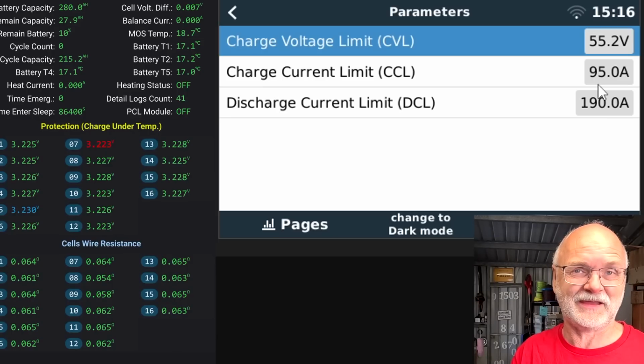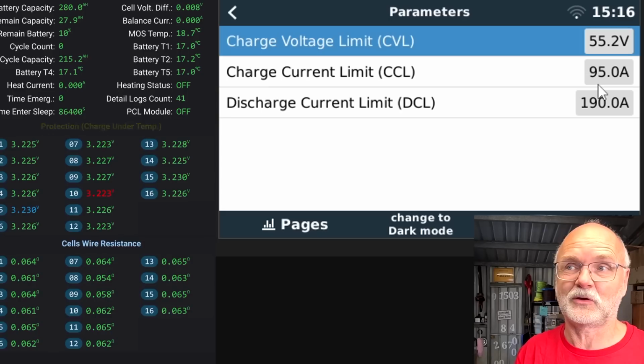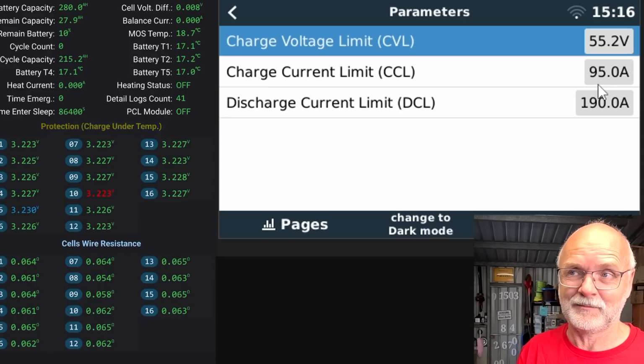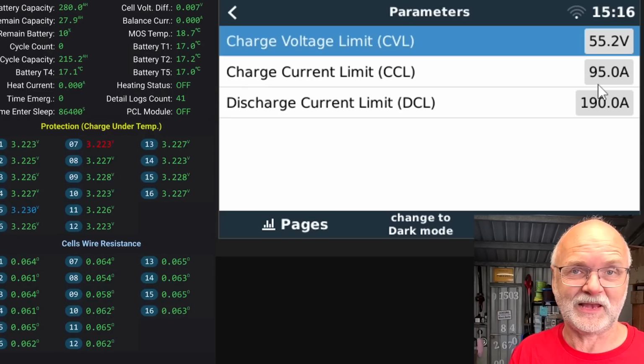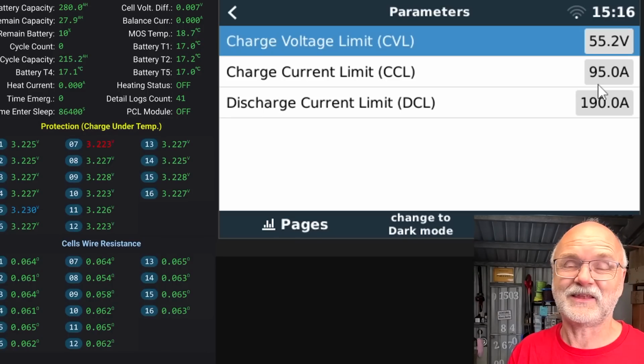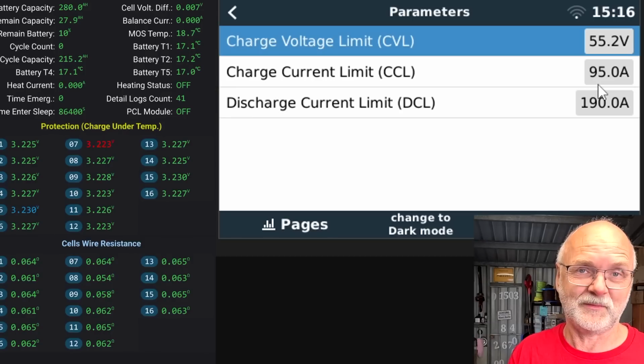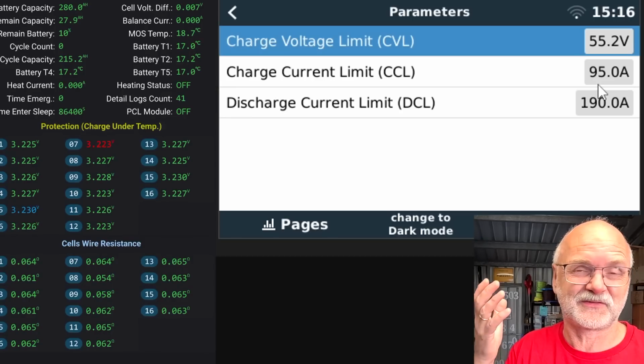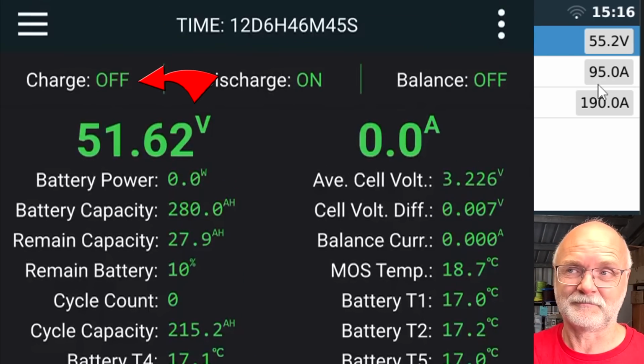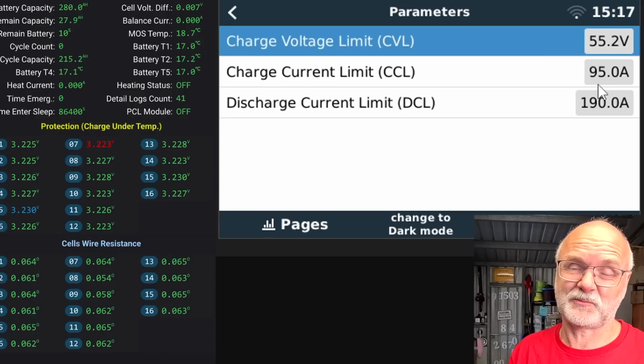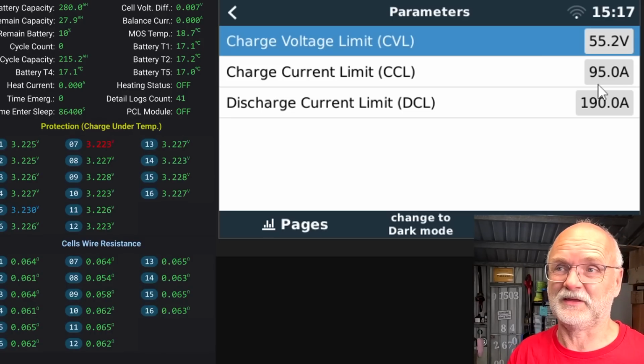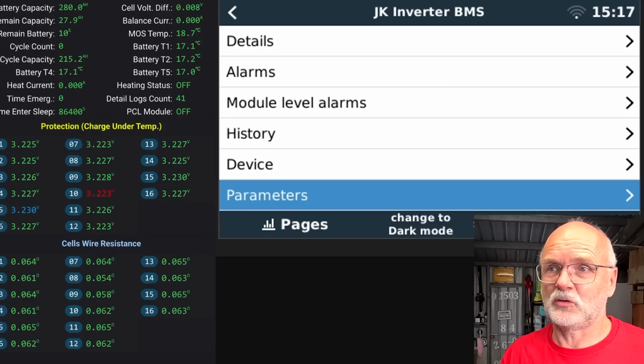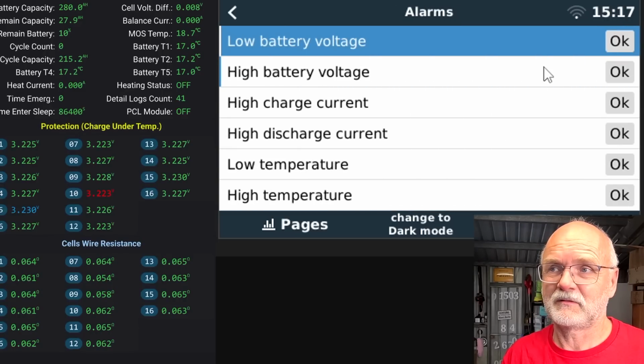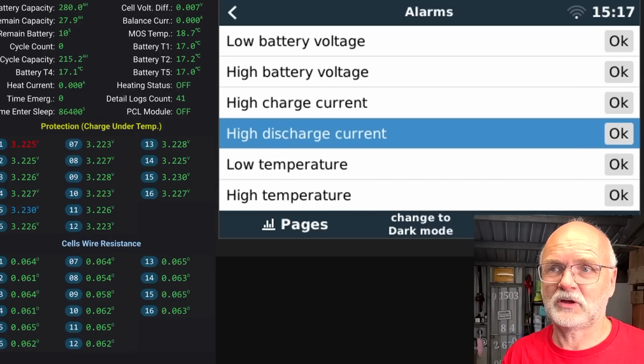Both BMSs could take the 100 amp set in the parameters. But now, because one has an under temperature alarm or protection, it reduces the available charge current to 95 amps. And it tells the inverter you can maximum charge with 95 amps because one of the batteries has a protection and the BMS is disabling charging. So the communication from this perspective works absolutely flawlessly, yeah? No problem at all. So if we go into alarms, we can see okay.